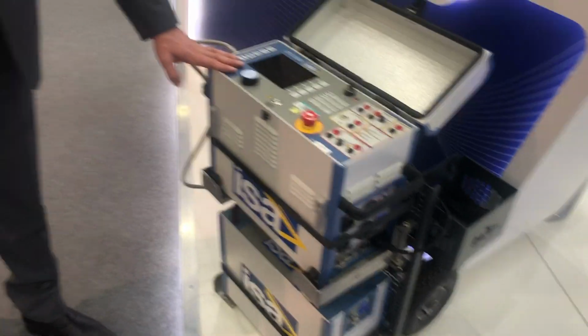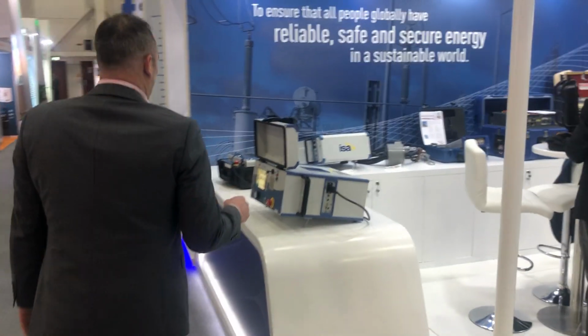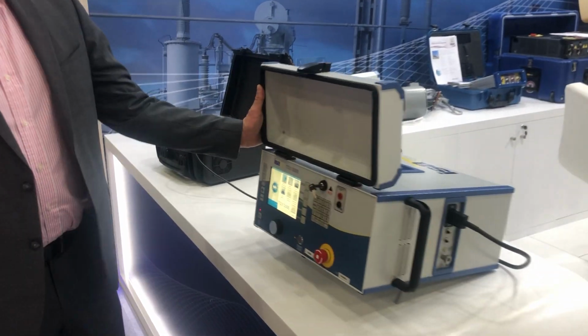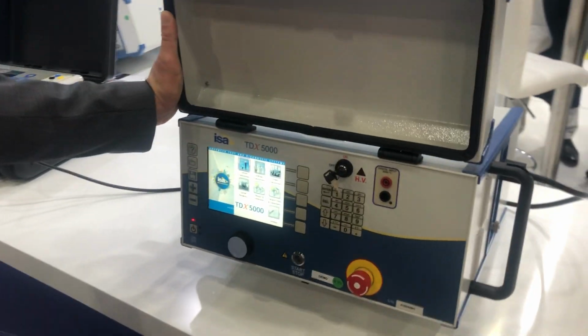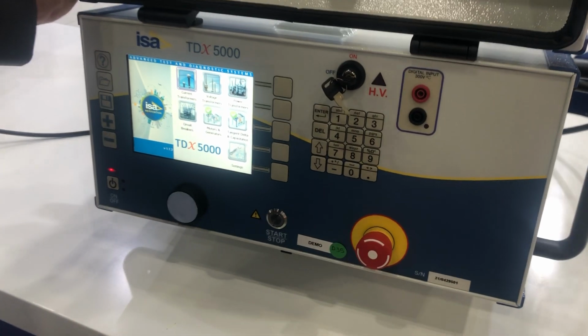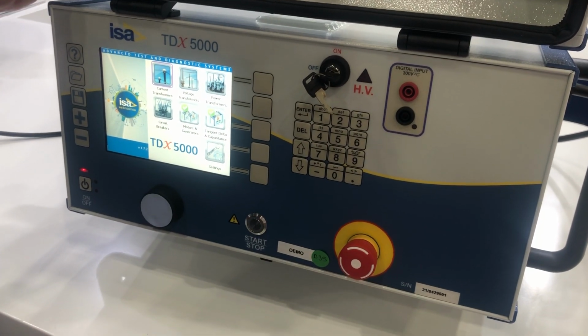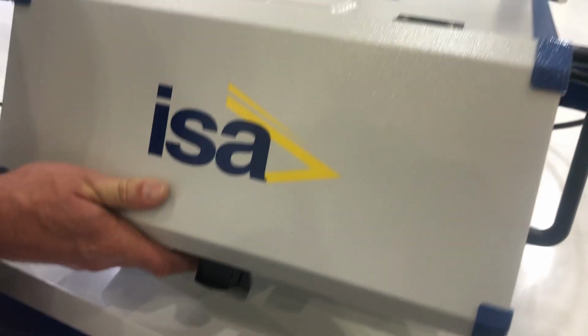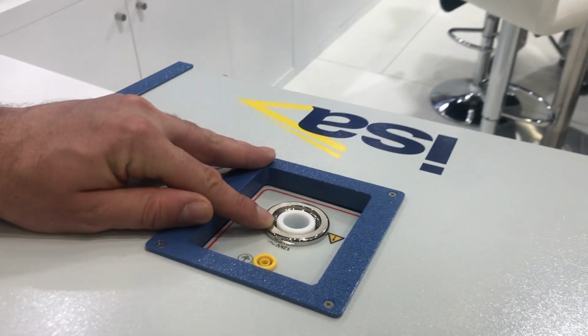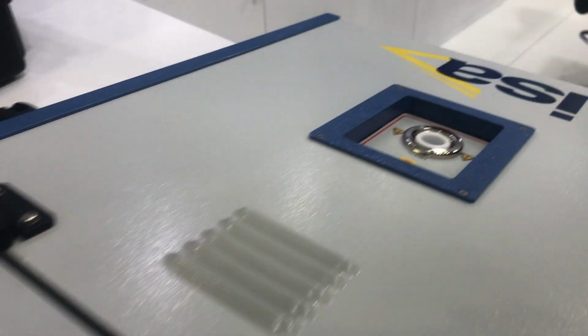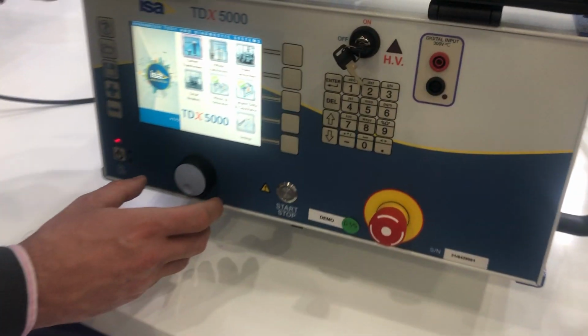Now this is a transformer tester. We have some more transformer testers. Well, actually this would be a tan delta tester, which is made for transformers, but you can also test shorter cables, generators and motors, so rotary machines. Generation is up to 12 kilovolts, like TDX 5000, which we have shown previously, and 300 milliamps. And the device is quite automatic.